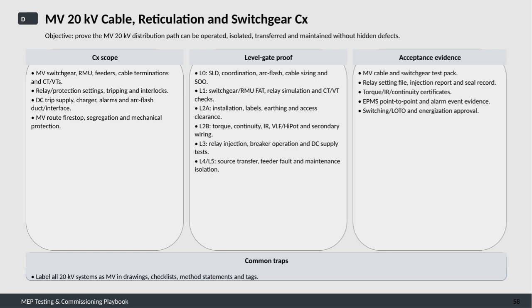The key objective here is to confirm that the entire 20 kV distribution path can be safely operated, isolated, transferred, and maintained without any hidden defects that could cause issues down the line. Starting with the commissioning scope, it covers everything from the MV switchgear and ring main units to feeders, cable terminations, and current and voltage transformers.